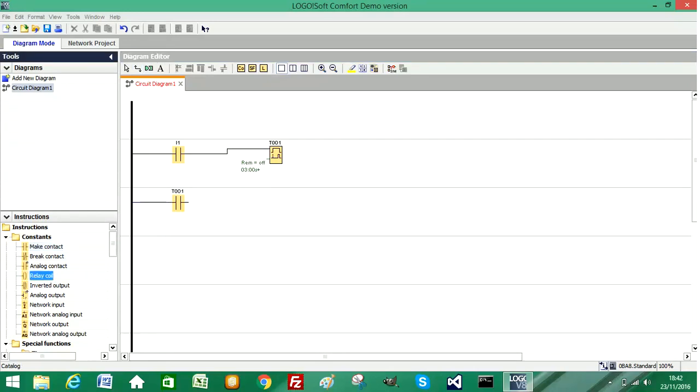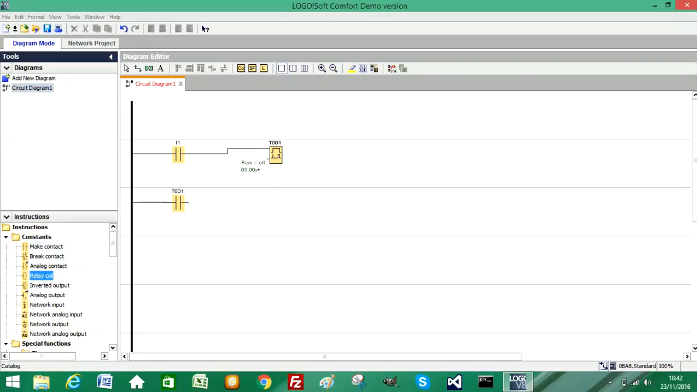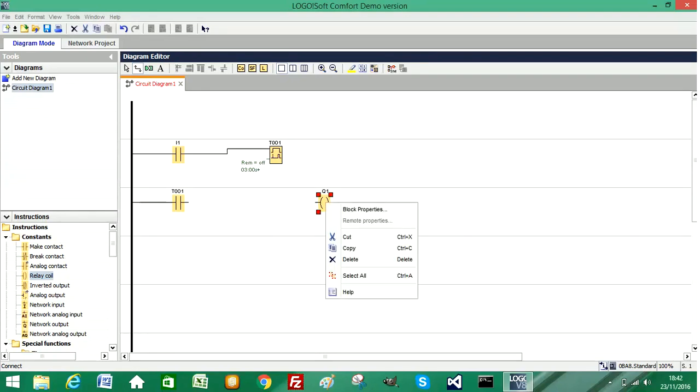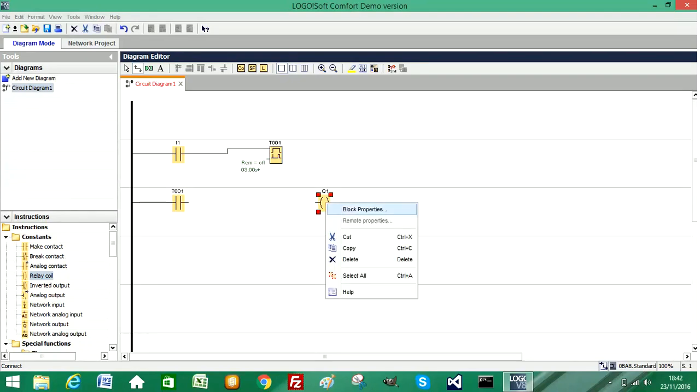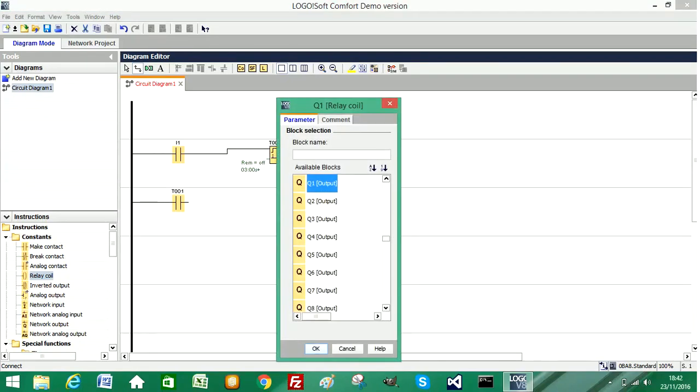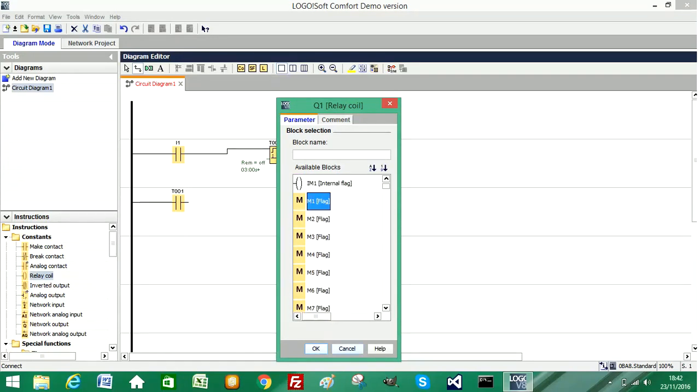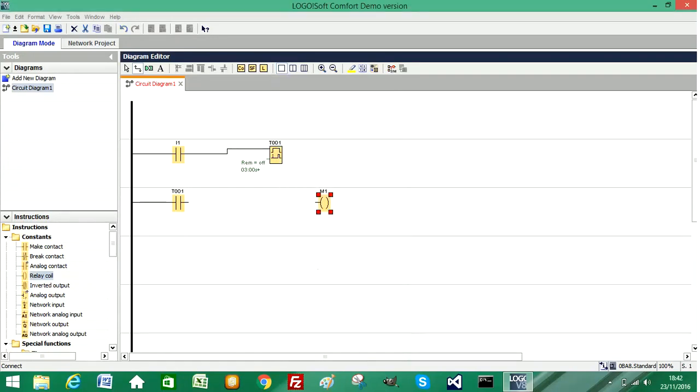So what this is doing is replicating the state of this timer. I'll wire this to the power rail and I'm adding in a relay coil so we can see our output turning on and off. I'm just going to select an internal memory bit rather than a physical output. So I'll select M1 and wire this up.